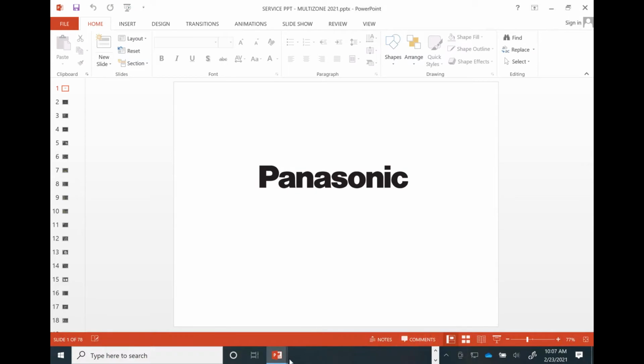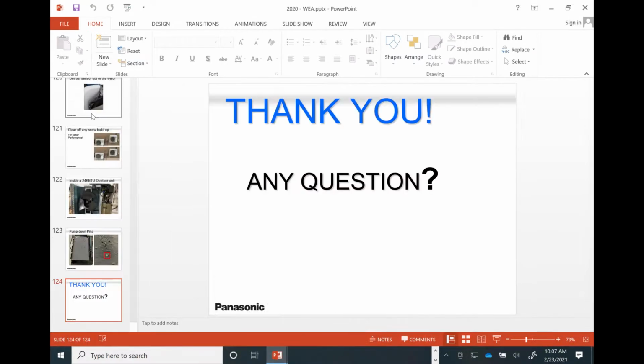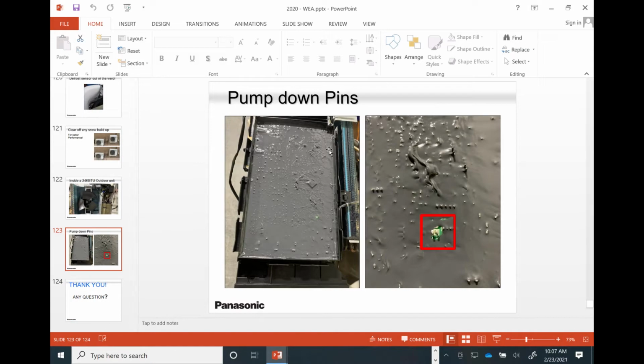For example, if you have an electronic coil problem, and that electronic coil has shot to ground, that can take out the outdoor PCB. And when it takes out the outdoor PCB, you can get a communication error. So before you decide whether it's the outdoor PCB or the electronic expansion valve, on this PCB you will see a spot burnt over here. If you see a spot burnt over here, rest assured that the electronic expansion valve killed this board. So when you're changing this board, replace also the electronic expansion valve.